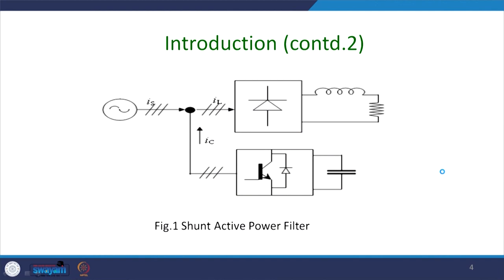This is the topology — the one-line diagram of the shunt active power filter. You have a source Vs, and thereafter mostly you have a small inductance, which is the source inductance and can be the leakage inductance of the transformer. Once you pass through a nonlinear load, the current profile will be distorted, and ultimately you have to inject the current in such a way that the load sees as if a resistive load is connected to it.